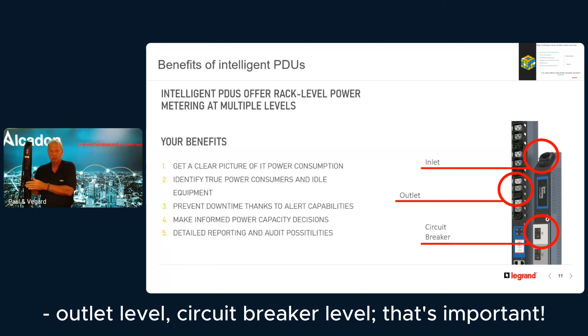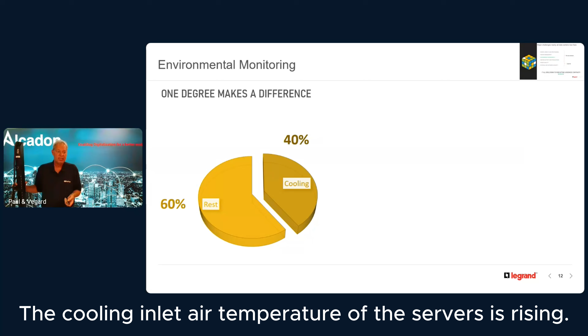Let's talk about temperatures. To save energy, to save money, companies are starting to raise the cooling inlet air temperature of the servers. Just to give you an example, if I raise my temperature from 25 degrees to 26 degrees Celsius in my data center, that's about 2 Fahrenheit, I can save on the cooling almost 10% of my total data center cost. Just by raising the temperature, the energy consumption of my air conditioning will drop. So warm is the new cool, I would say.